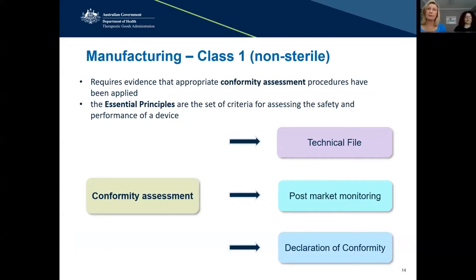So the conformity assessment procedures for Class 1 non-sterile PPE are broken down into three steps. The whole goal is to ensure the manufacturer demonstrates compliance with the essential principles. Those essential principles, or EPs, are a set of criteria for making sure the device is safe and performs as intended.